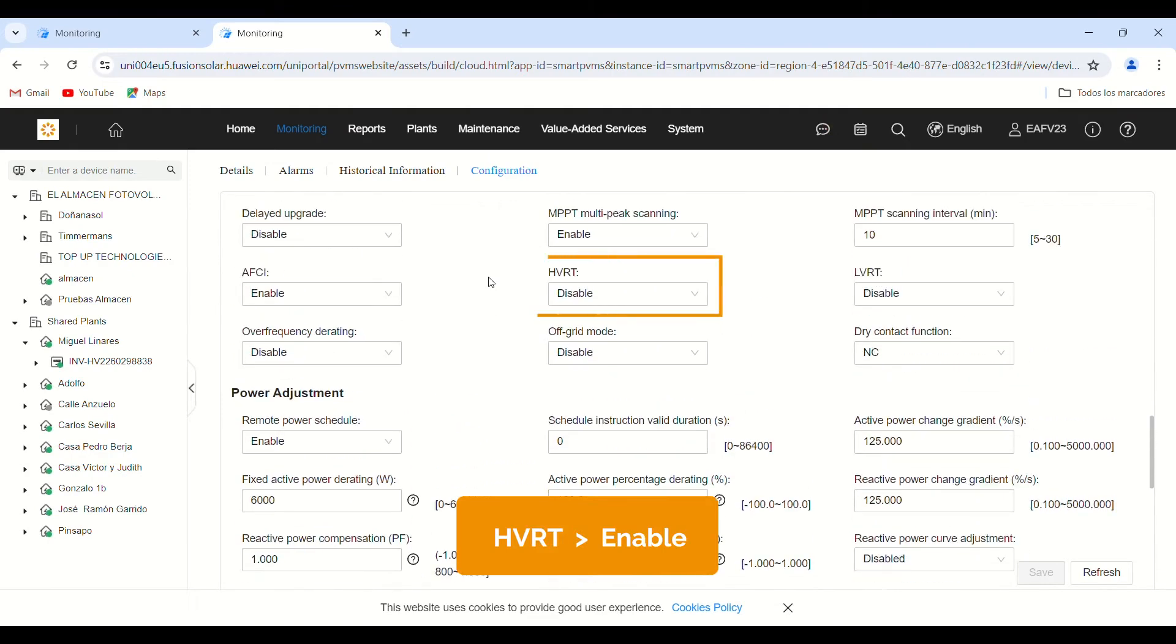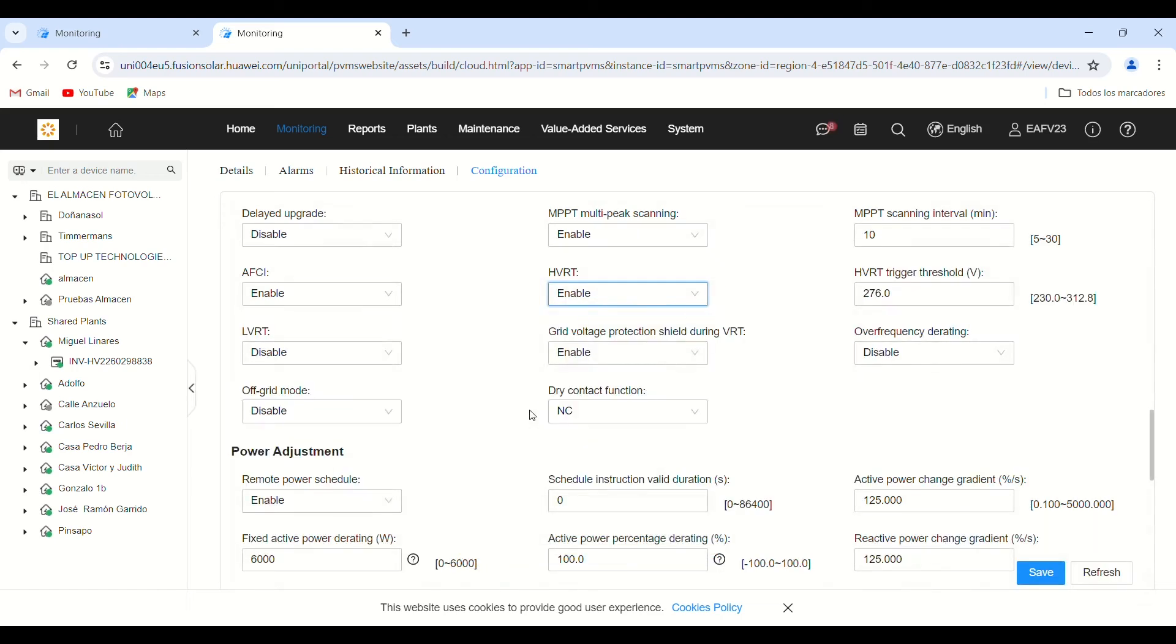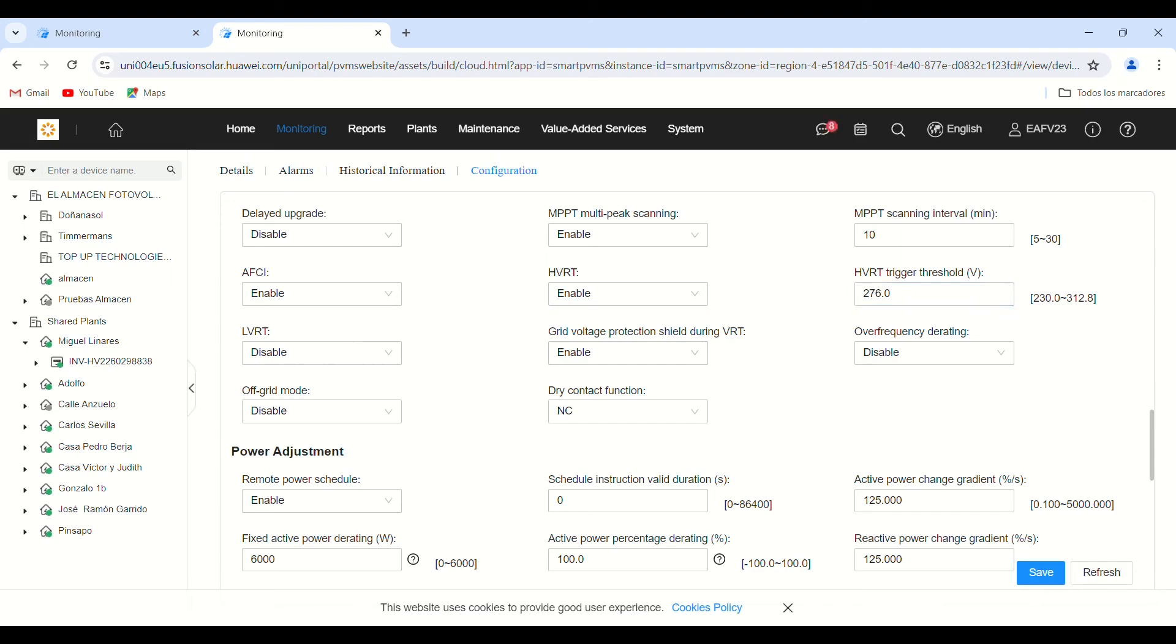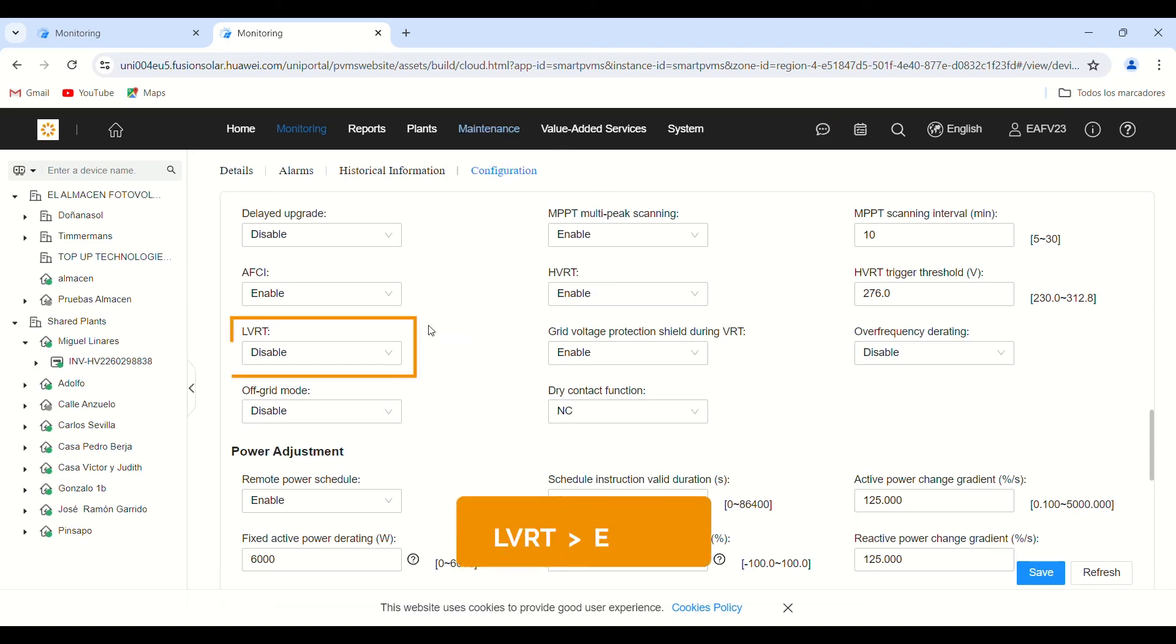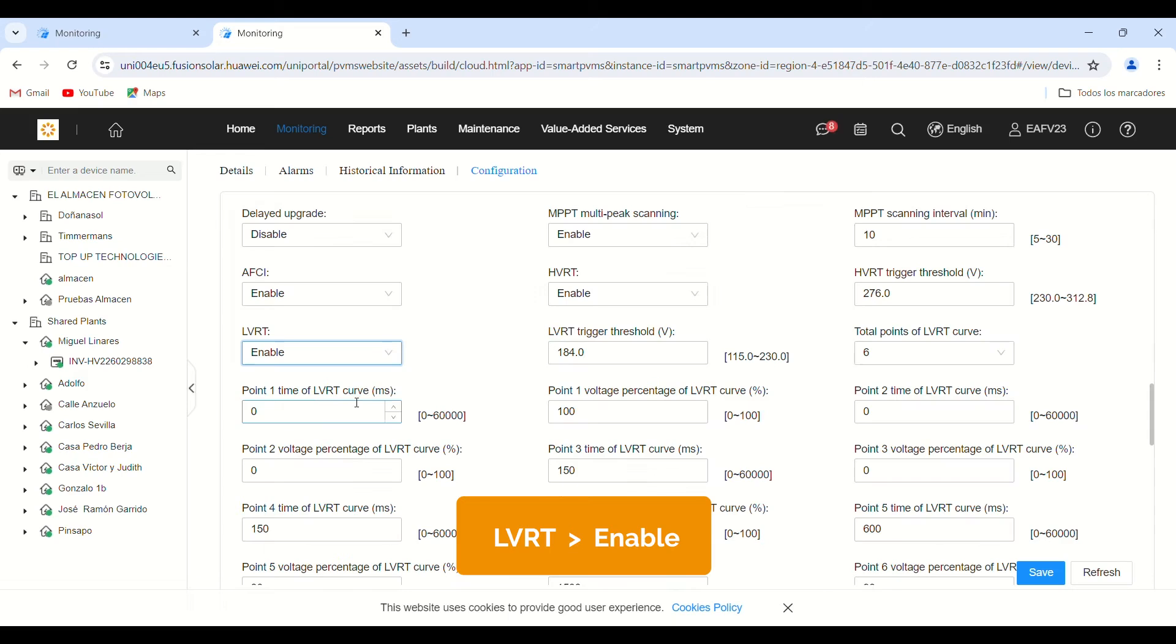HVRT stands for Maintenance of Connection in case of voltage increase, if the grid voltage is abnormally high for a short period. Activating this parameter can eliminate the shutdown due to overvoltage peaks. It is recommended to leave the additional parameters that appear after activation in their Huawei default settings.